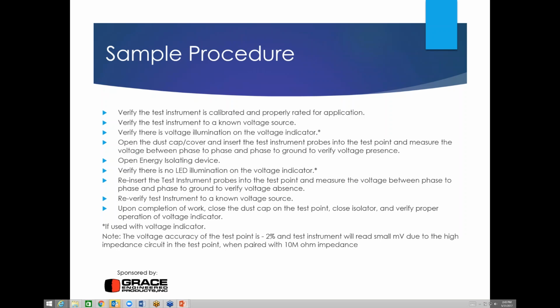Next, you're going to open the energy isolating device, and verify that there is no LED illumination on the voltage indicator. The reason that we're going to verify it there first is because that's going to continue to flash until we have bled down all of that energy that may be stored in capacitors in the system. Then we're going to reinsert the test instrument into the probes and measure phase to phase and phase to ground, verifying that there is no voltage. Then we're going to take our voltmeter back to that known source and verify that it is still working.